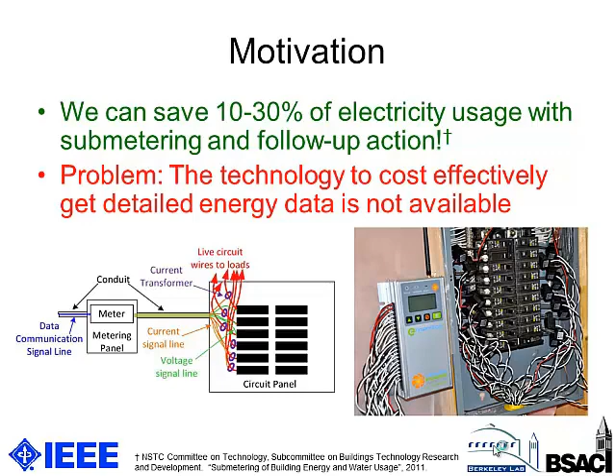So now you see this acronym SEM. I'm going to use that through the rest of the talk, and that means StickOn electricity meter, not scanning electron microscope. And so these SEM sensors are non-contact based sensors that measure both voltage and current, so they can calculate real power. And these sensors are installed on the external face of the circuit breaker. And so all these sensors are connected together with a wired bus. And this wired bus then connects to a panel base station, which transmits all the data out wirelessly.